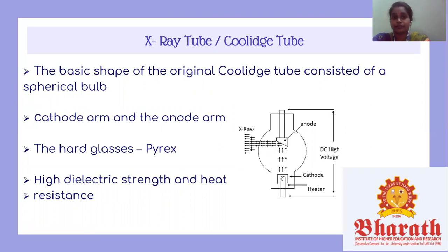the opposite sides, the cathode arm and the anode arm. The arms increase the dimension of the tube so as to avoid electrical arcing from one end to the other. The length of the arms also helps prevent stray electrons on the inside of the tube from getting close to the tube ends. The bulb is also large so as to increase the surface area from which the tube radiates heat. In addition, its large size reduces the amount of tungsten that can be deposited per unit area, and it keeps the glass away from the strongest portion of the electrostatic field.